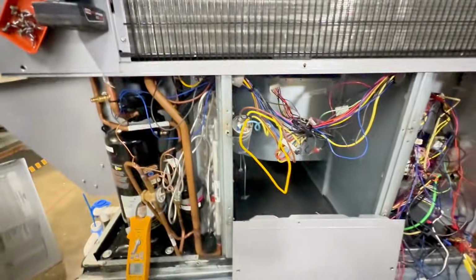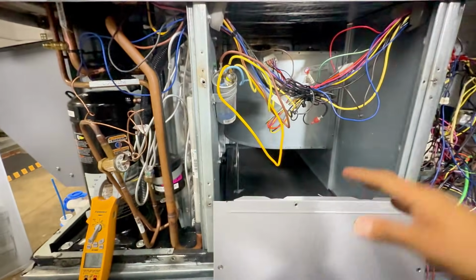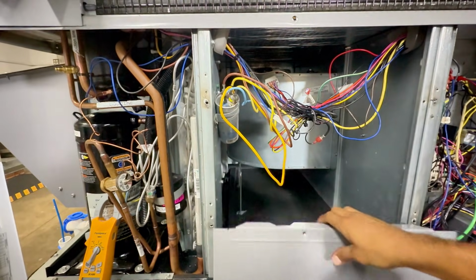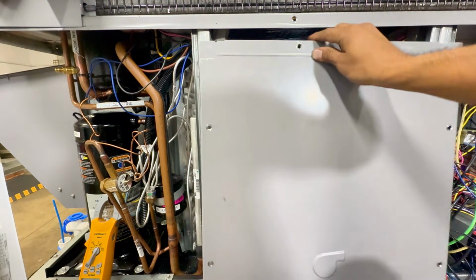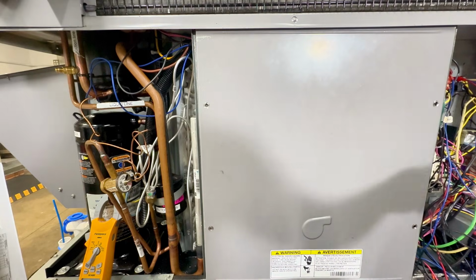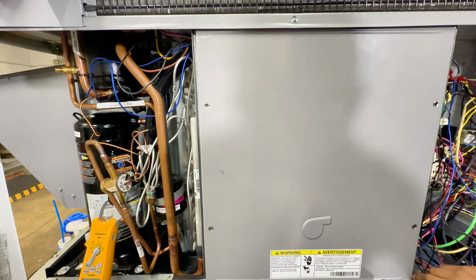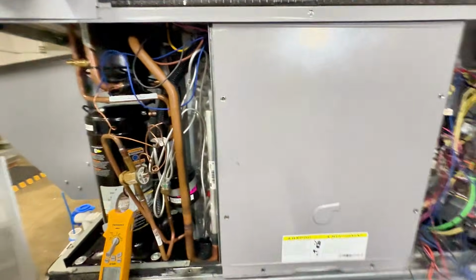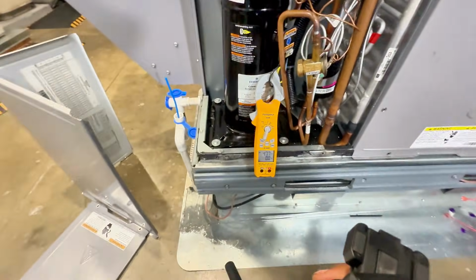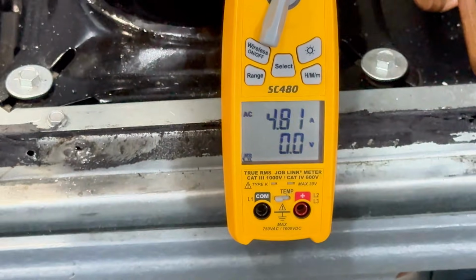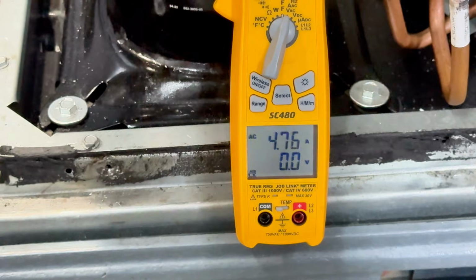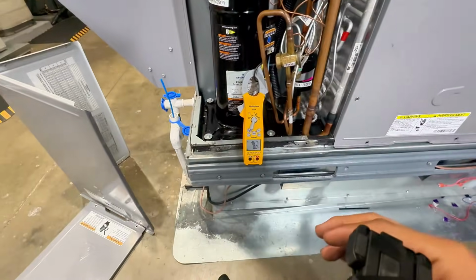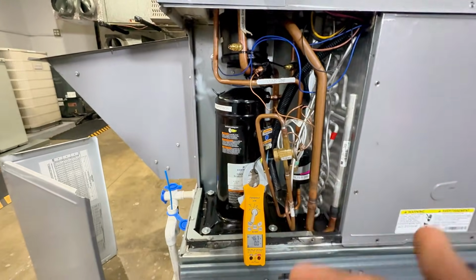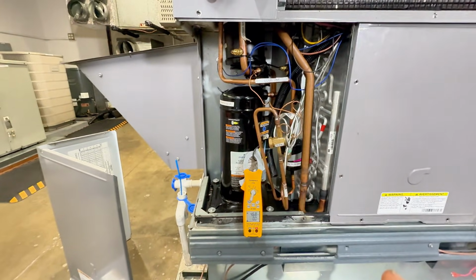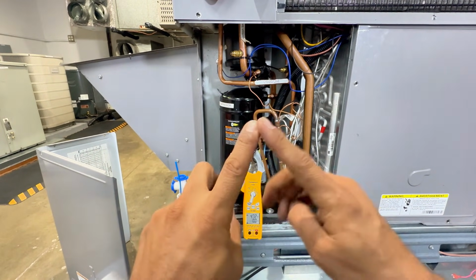Whenever you check your compressor, airflow has to be good. So I have to close this. If not, it's going to give me some weird numbers. So now let's go back and see what we're getting now. 4.8. So we're not pulling a lot of amps. Now have in mind though, I think this system might be undercharged, but this is the point here though.